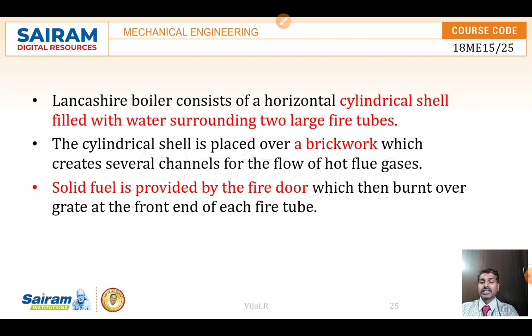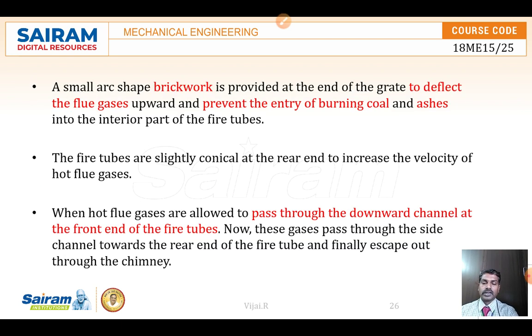Now we are concentrating only on the Lancashire boiler. It is a cylindrical shell filled with water, and there are two large fire tubes through which the hot flue gases are going to pass. The solid fuel we are burning at one fire door, where we are firing that fuel. The brickwork is provided to deflect the flue gases and to prevent the entry of burning fuel and ashes into the interior parts of the tubes.